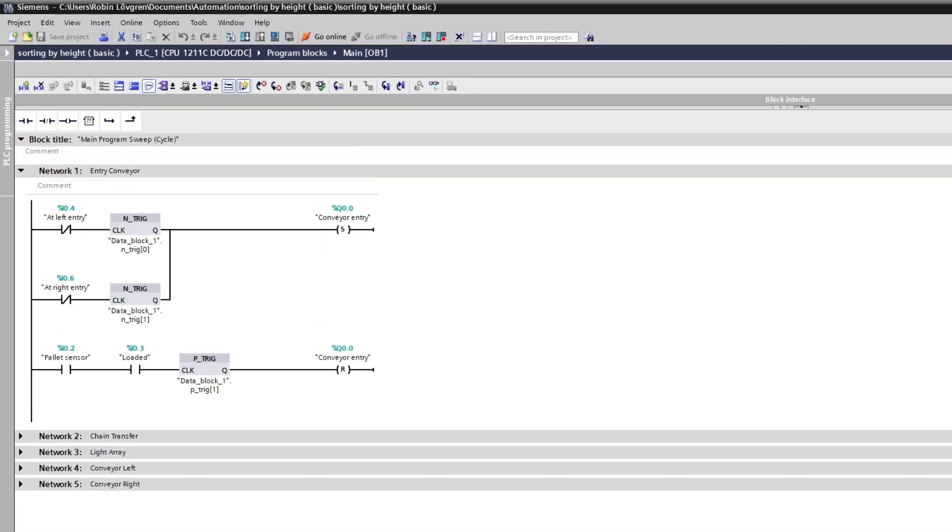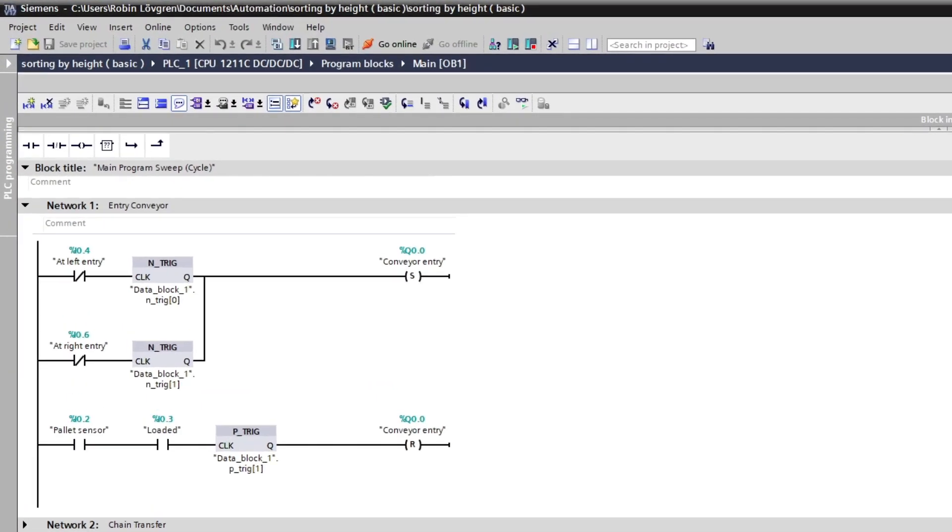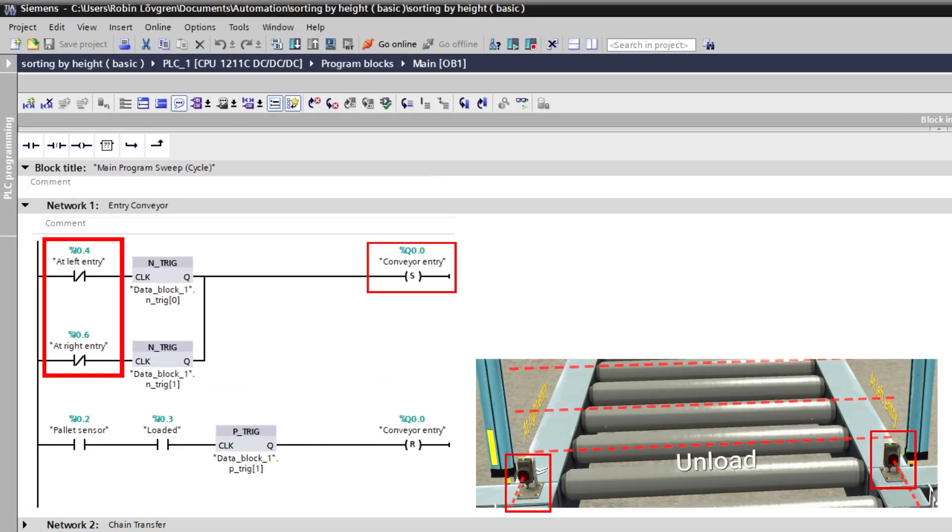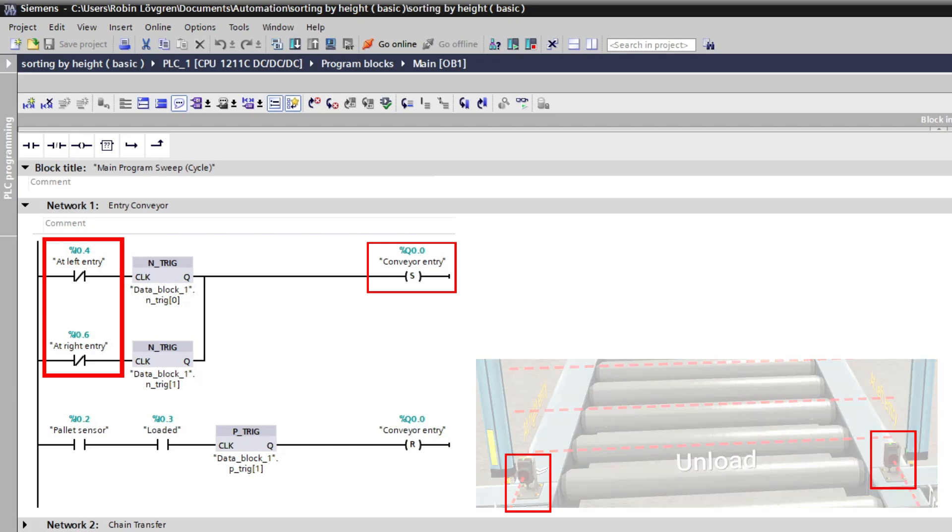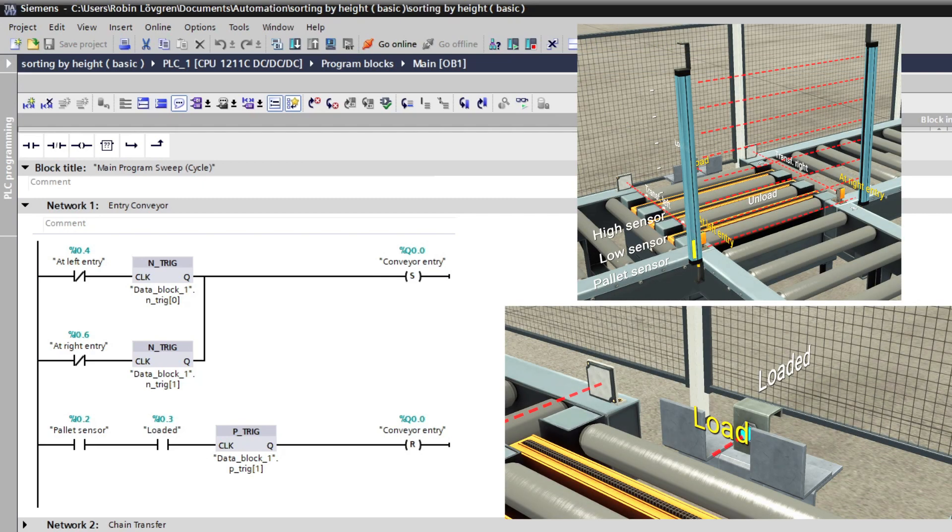This is the code needed for the entry conveyor. When a pallet passes by either the left or right entry sensor, then the entry conveyor should be set. And to keep it fully automated, it will only be reset when the pallet sensor and the loaded sensor get occupied.